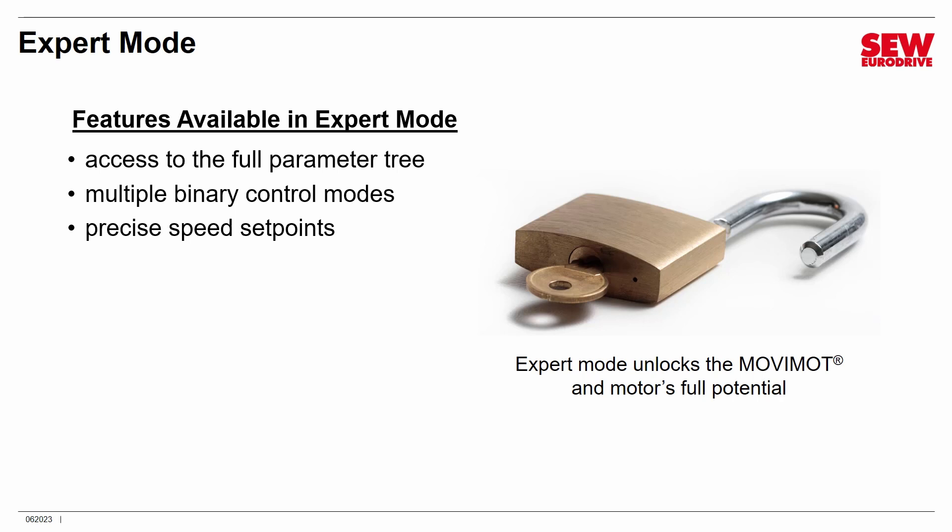You get precise speed set points. In Easy Mode, speed set points depend on the F1 and F2 dials, and you can't always set those to exact speeds. Expert Mode lets you key in an exact speed — for example, you could set 806 RPM precisely. There's also a mode that gives you access to four fixed set points instead of two, which is useful if certain applications need more than two speeds. The only way to do that is Expert Mode or RS-485 mode.